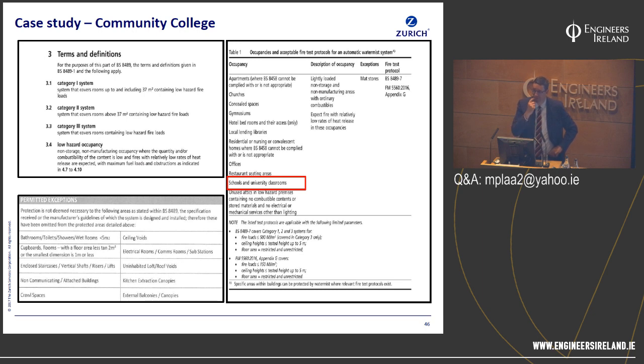Yeah, because the outcomes aren't equivalent. No. Each occupancy, each area has to have independent fire test data. So the fire load in a gym store with all foam mattresses will be different from a school and university classroom. What about the roof voids? If we have a fire in a roof space which is not protected, that's going to go unseen and spread through the whole school. We'll lose the whole school. So there are some serious implications to picking and choosing exceptions.